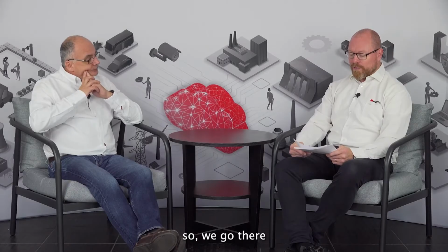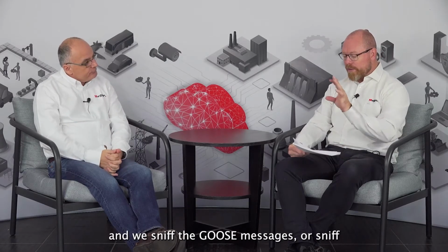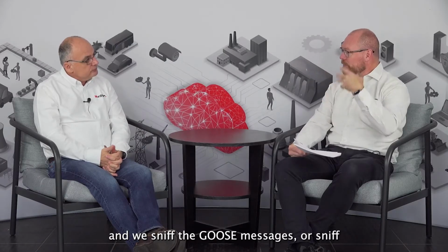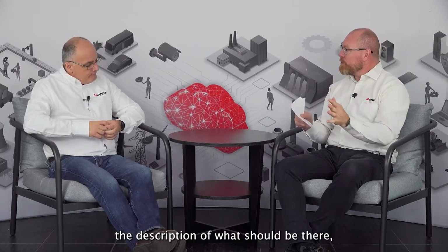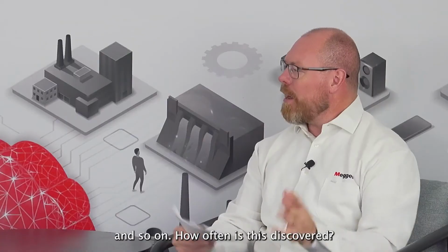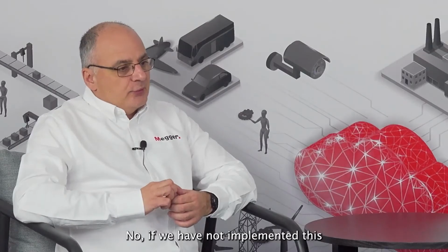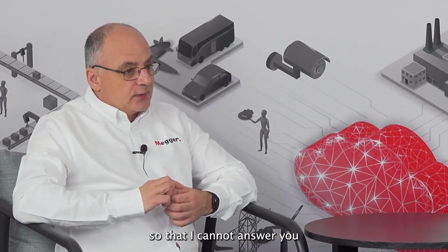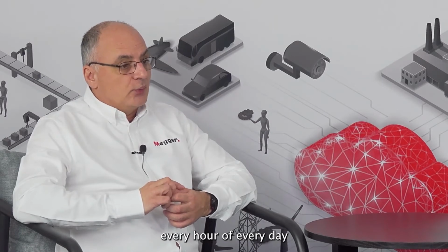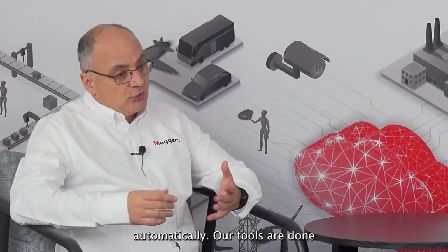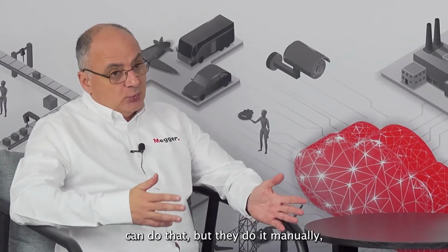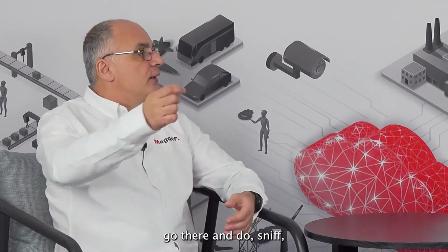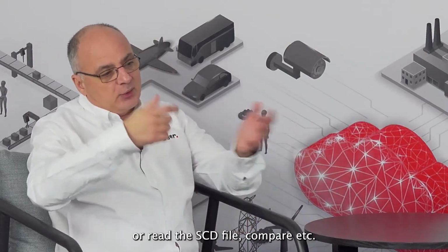Interesting. So we go there and we sniff the GOOSE messages, or sniff the network, to see what messages are there. We have the description of what should be there, we compare, and so on. How often is this discovered? Is it daily or is it never? No, we have not implemented this automatically, so I cannot answer whether we do this every hour or every day. Our tools can do that, but they do it manually. So you have to personally go there and do the sniff, read the SCD file, compare, etc.